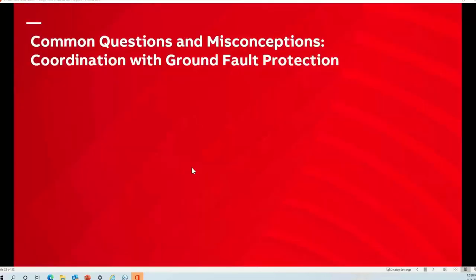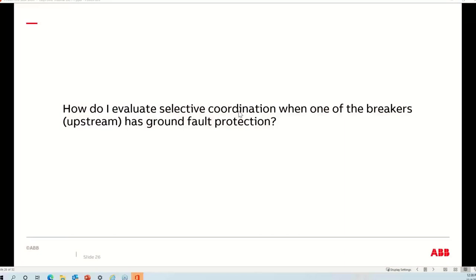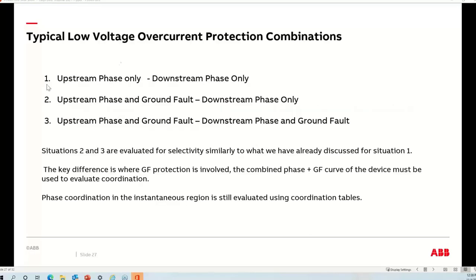Next, I'd like to talk about ground fault — another common question. How do I evaluate selective coordination when one of the breakers — typically the upstream — has ground fault protection? To this point we've focused on upstream phase to downstream phase. But there are other combinations involving ground fault that are evaluated similarly. The major difference is you now have to consider the combined curve of the ground fault curve along with the phase curve when evaluating coordination with the downstream breaker.